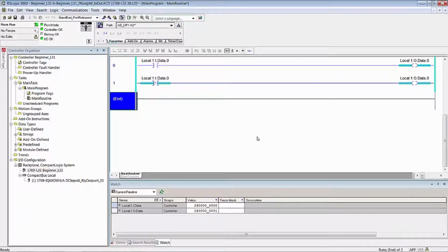So my point is, in 500 or 5 land, the landscape did not radically change very often, maybe once every 5 or 6 years. With RSLogix 5000, and remember that the rev level of the controller has to match the rev level of the software, the app that you're using, what you're looking at right here, they have to be the same.